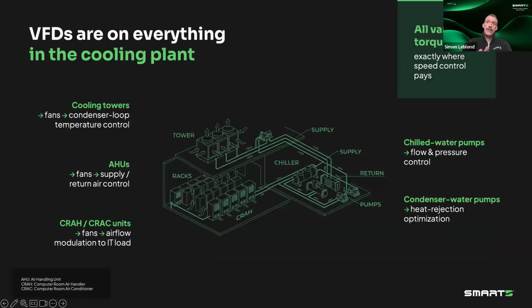And really, it applies across the cooling plant in the data center. You've got so many variable torque loads in there. Not necessarily that I want to go in details at every level, but whether you're talking air handling units, chilled water pump, you really have a lot of opportunity to take advantage of the affinity law, which I'm sure everyone knows about, but really cubic relationship between the energy you provide and the flow. That's where your biggest energy savings come from and your dollar value.